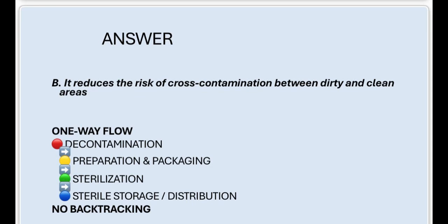The answer is B. It reduces the risk of cross-contamination between dirty and clean areas. SPD workflow should progress from contaminated activities towards clean preparation and ultimately sterile storage and distribution. We don't want contaminated instruments traveling backwards into clean areas.